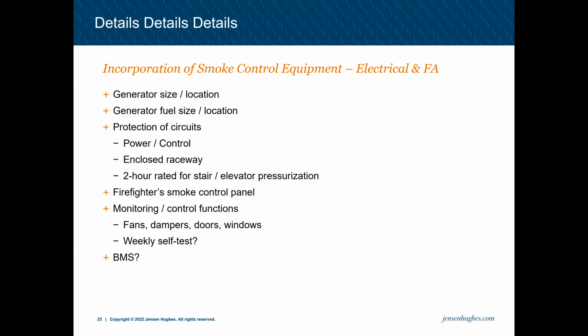Also in the monitoring and control functions, something that we should talk about is that smoke control systems must be tested semi-annually, which we'll go into. But smoke control systems also must run a weekly self-test. And that is an automated test that verifies the function of the smoke control system are working correctly, which might not be a big impact. However, these smoke control systems move a lot of air. And having these systems run automatically once a week can be very detrimental to a building owner.